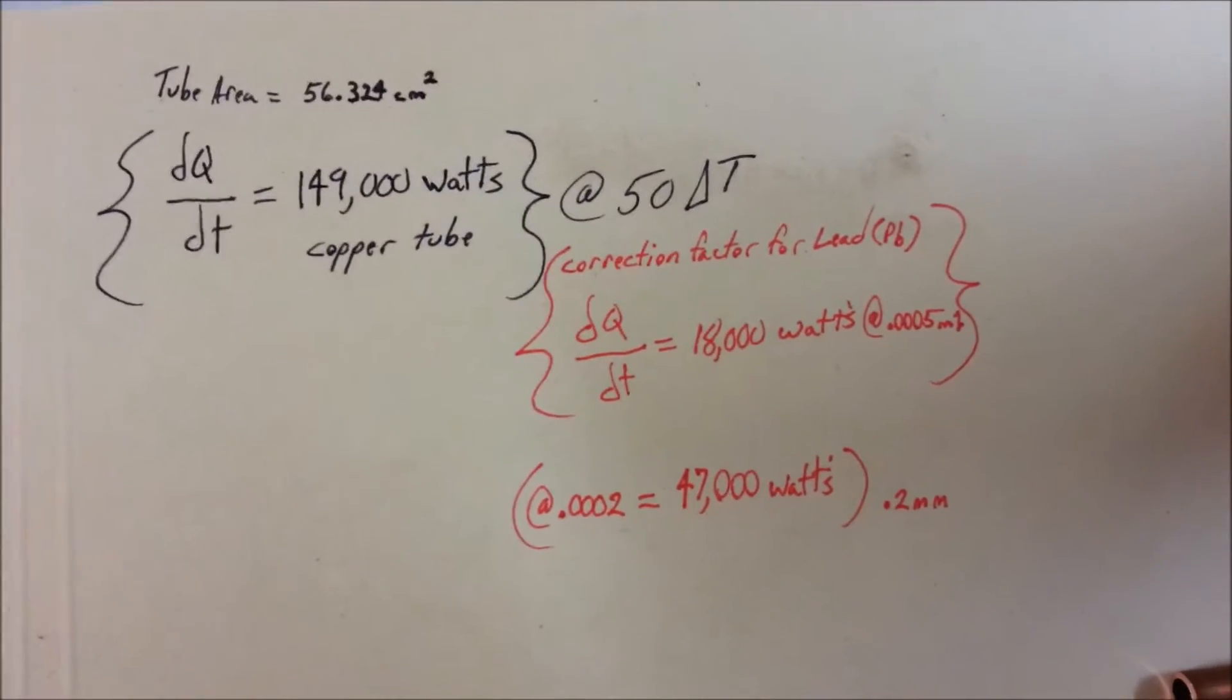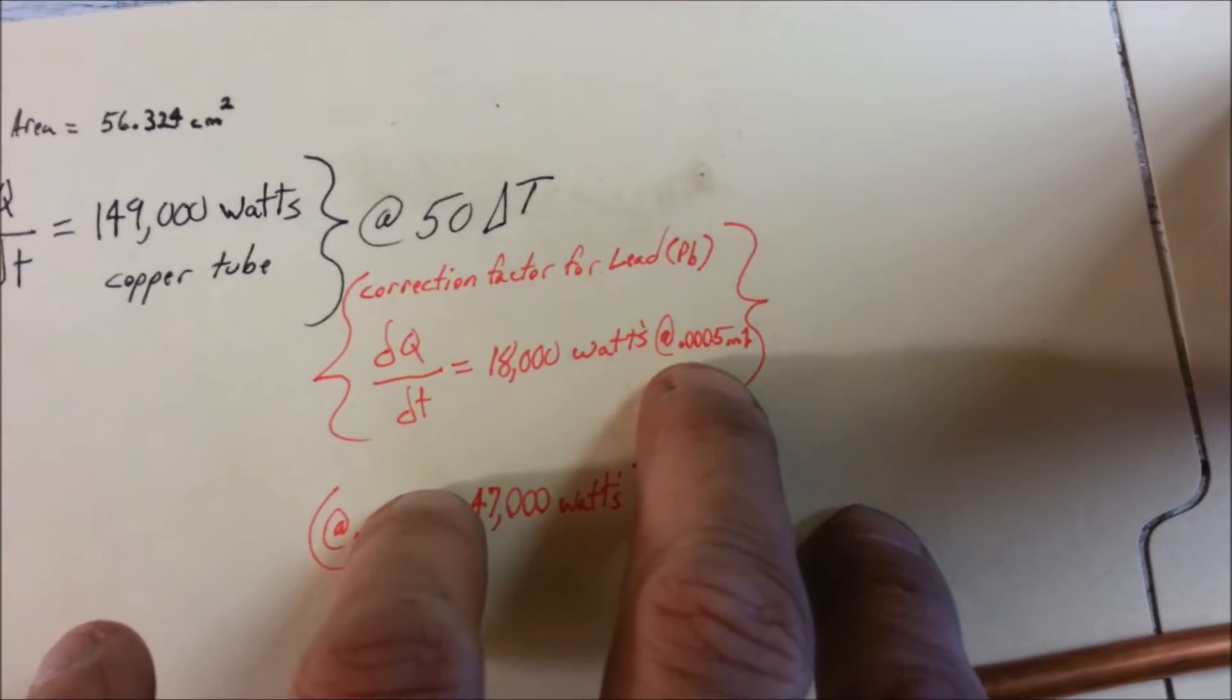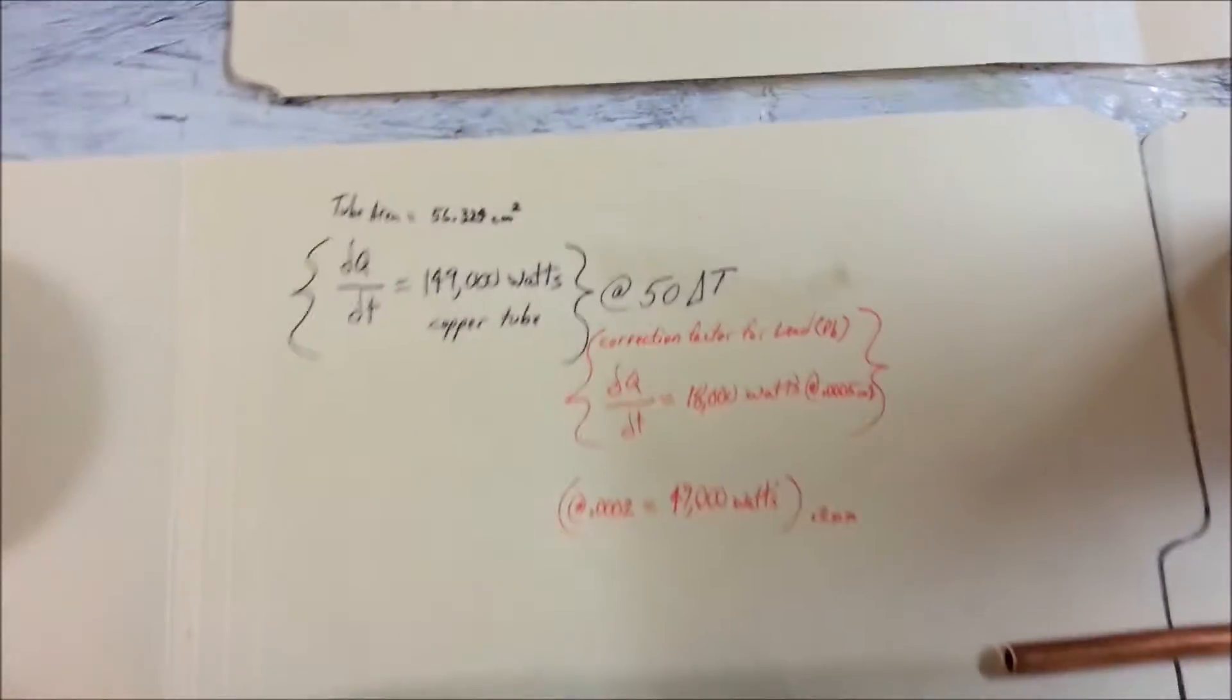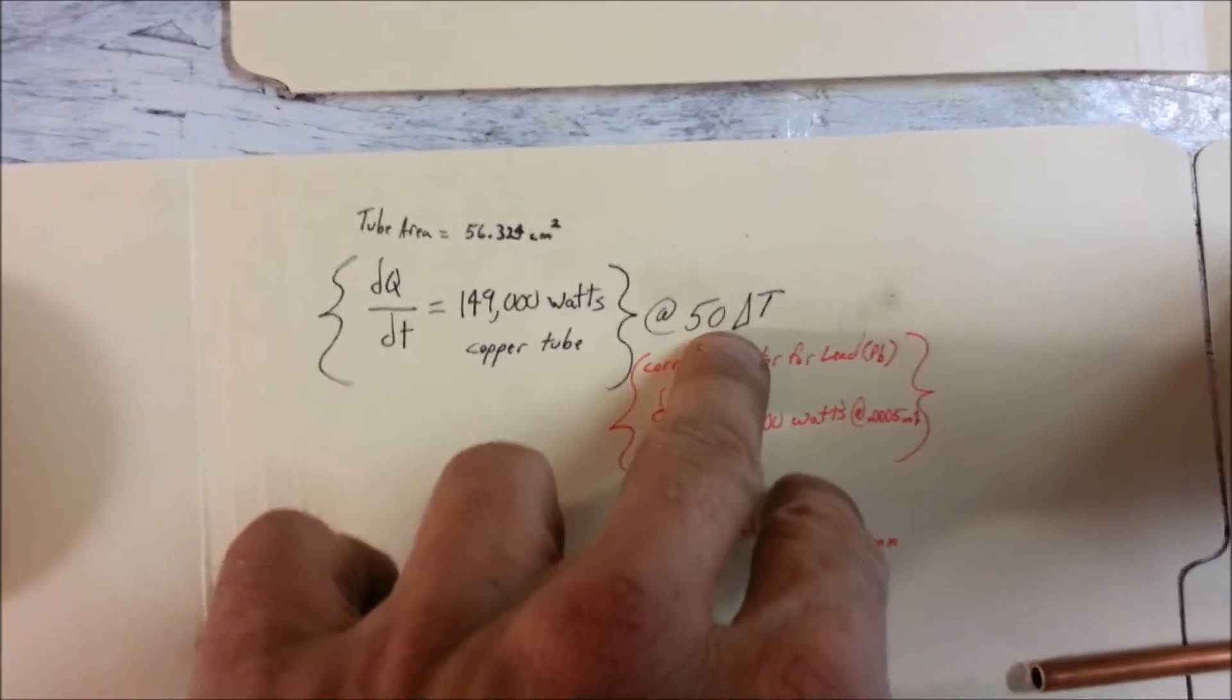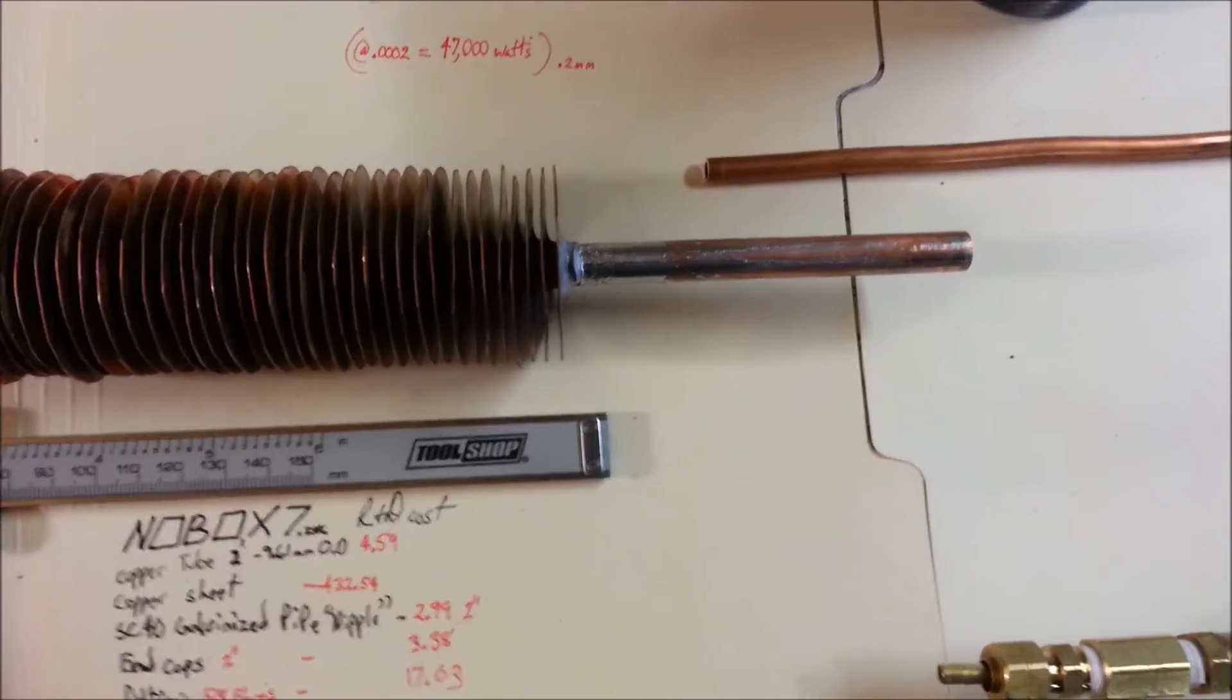Turns out that because I use lead solder, I'm actually limited to 18,000 watts at a 0.5 millimeter thickness of solder. As you can see on this unit, there's quite a bit of lead solder. It's actually a tin lead alloy. And I did not look at the thermal conductivity constant of tin. But I think for a test apparatus this will suffice. But again, if it were all copper, the tube alone would be capable of transferring 149,000 watts a second at a 50 degree temperature change.